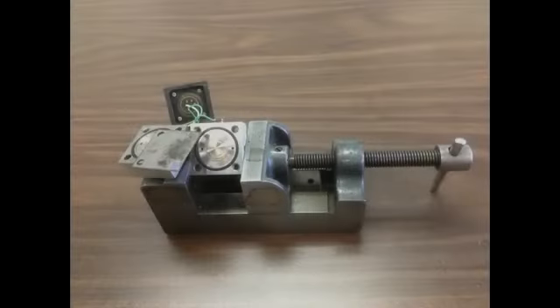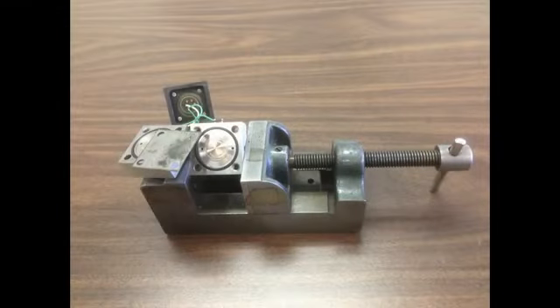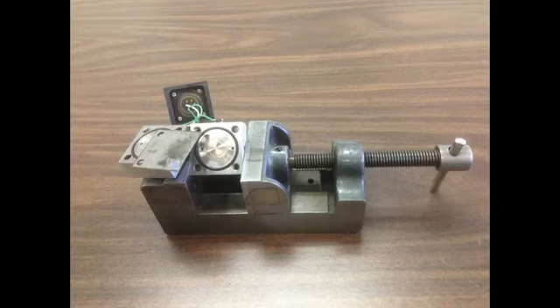When the sensor is apart the sensing diaphragm will drop out, and you will see two O-rings in the sensor body. Inspect the O-rings to verify that they have not been distorted or been eaten by corrosive fluids. New O-rings are available from Validyne.